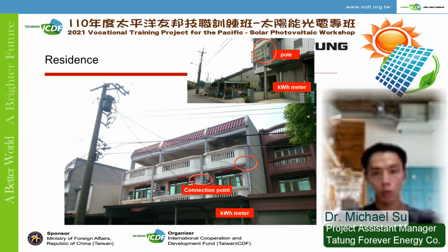Some of the entry points are set directly on the wall of the residential house. Sometimes they put another smaller pole right next to the house for the lower voltage entry cable. Either way, there will be an electrical meter by the entry point. Therefore, once we arrive at the new site, the best way to find out how many transformers they are connected to is to count the meters. This is the case of residential areas.